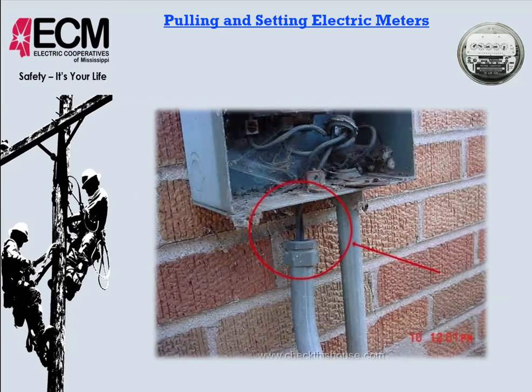So here's a common problem here too with the meter base, is that it was probably originally done correctly, and this is probably the underground entrance cable, and it goes down and probably has a 90 on the bottom, and as the ground settles, the weight of that on that 90 pulls this out of there and pulls the next size knockout with it. And probably not something we're going to fix, but require one of our consumers.